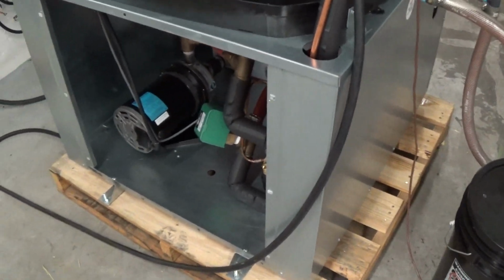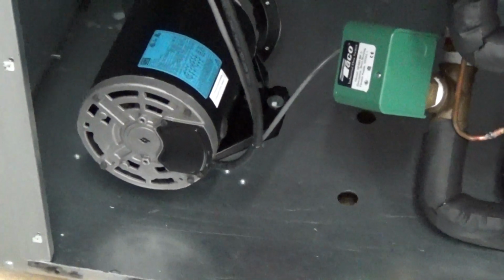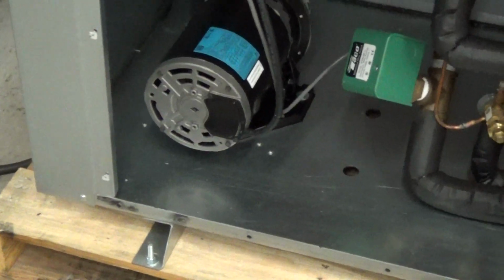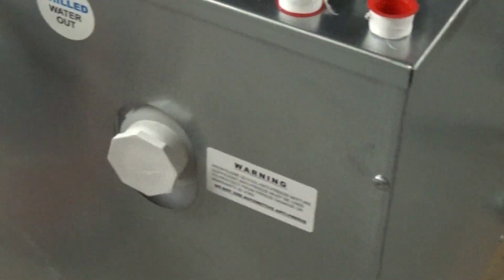When you first get the unit, you want to check the rotation of the pump, and this is a 3-phase pump. To do that, you'll toggle the power here while you have somebody looking at the back of the pump to make sure that the pump is spinning in the right rotation, which will be clockwise when looking from behind, like I am right now. Or you should be able to also bump the contactor. That's another way of doing it. But usually you need 2 people, and sometimes you need a flashlight down there to look at it. So we're going to turn the unit on right now. We have the tank full, and obviously never run the pump unless your tank is full. And this is the fill port for the glycol tank.